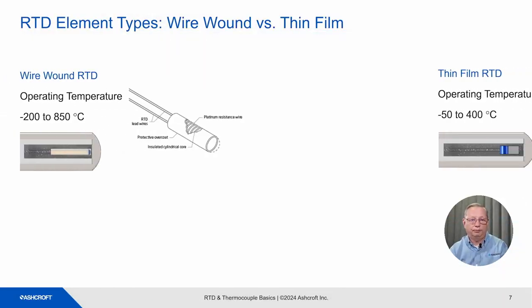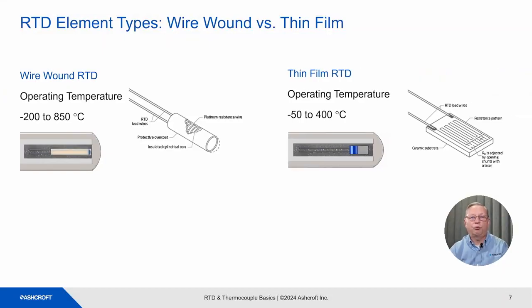There are two types of RTDs, wire wound and thin film. Wire wound are a wound coil of platinum wire. They have a wide operating temperature range of minus 200 to 850 degrees C. Thin film is made with a platinum resistance pattern on a ceramic substrate with a narrower temperature range of minus 50 to 400 degrees C.